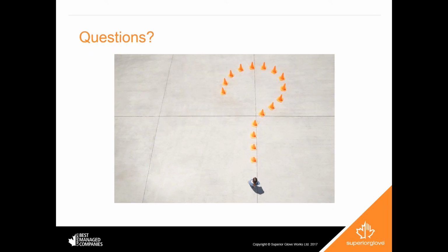As Matt mentioned earlier, depending on what level you're at as far as the ratings and the cal ratings, it can be as simple, if you're at a very low cal rating of 4 or less, as simply wearing 100% cotton clothing could be the adequate protection that you need. I always tend to err on the higher side and say I want a little more protection than maybe is needed. But there are specially treated garments, made from treated cotton or Nomex or a Kevlar base, that are designed for these, because in some of these severe industrial environments, you're talking about some extremely high voltage possibilities where arc flashes are going to exceed these temperatures that we mentioned earlier of 35,000 degrees Fahrenheit.